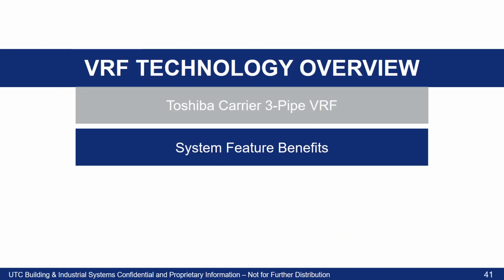Hey, Kevin, I don't remember if you had this in your slides or not, but the question is, must the VRF unit be outdoor or can it be mounted indoors in a mechanical room? We can do indoor. So really what happens there, they're going to be in a mechanical space that has a large exterior wall, right? They'll never be mounted indoors, I've never seen it that way. So they'll be on an exterior walled room. Essentially, that whole exterior wall will be louvered for the incoming condenser air, and then you'll have a louver right above that intake louver, which will be ducted to the outlet of those condensing units. So yes, to answer your question, we can do indoor unit installations. Could get into the weeds a lot more on that, but we can do it.